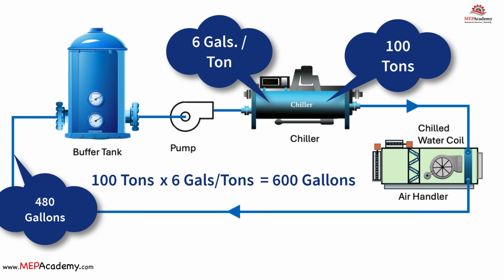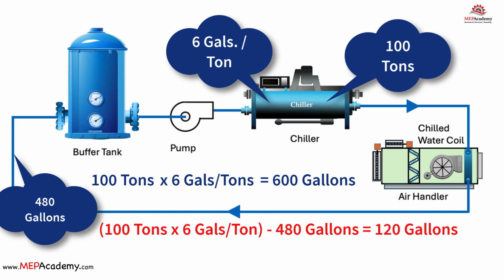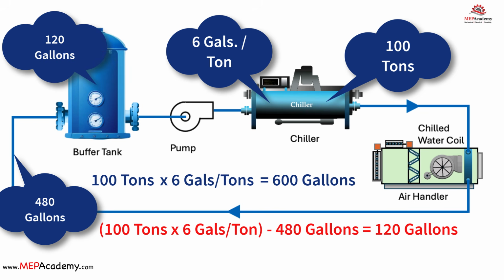Chilled water buffer tank calculation. Chiller buffer tank volume equals 100 tons times 6 gallons per ton minus 480 gallons equals a 120 gallon buffer tank. From the calculation, we can see that for every gallon the existing system total is under 600 gallons, another gallon is added to the tank capacity to provide the minimum required of 600 gallons of system volume.